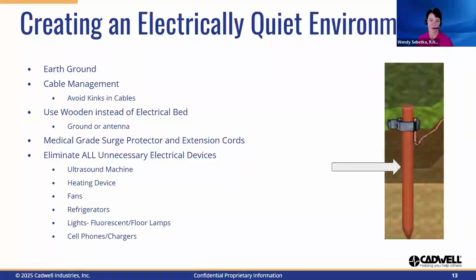Lights are a common source of noise and can easily be determined by turning the lights on and off. Blown bulbs or lights that have not been securely tightened in the sockets can be a new source for noise. All electrical devices emit signals that can infiltrate our responses. Special attention should be paid to remove all unnecessary devices from the area. This includes additional medical devices such as ultrasound machines, heaters, warming devices, fans, refrigerators, and even cell phones and chargers.